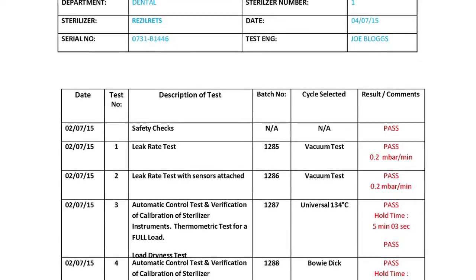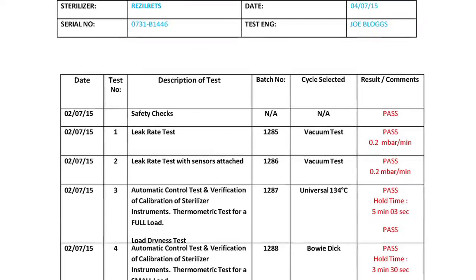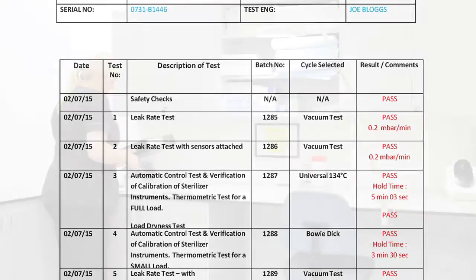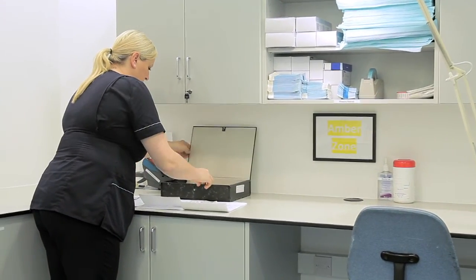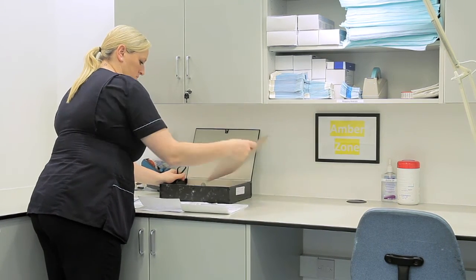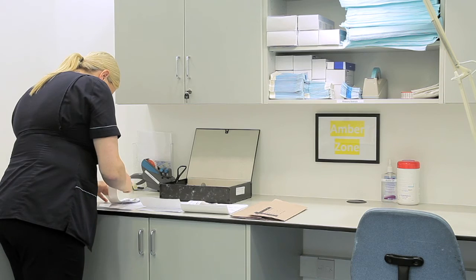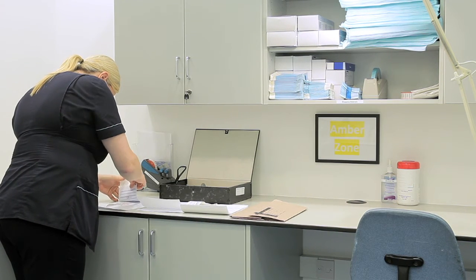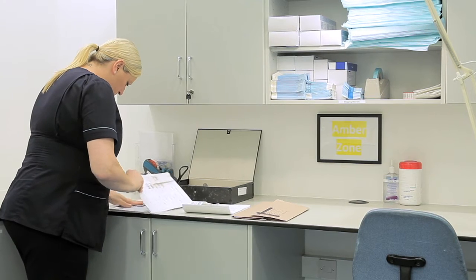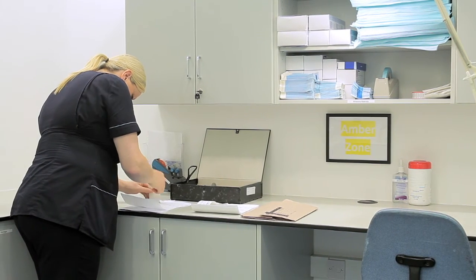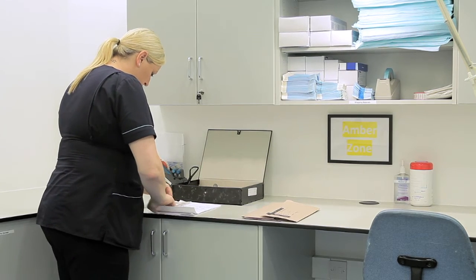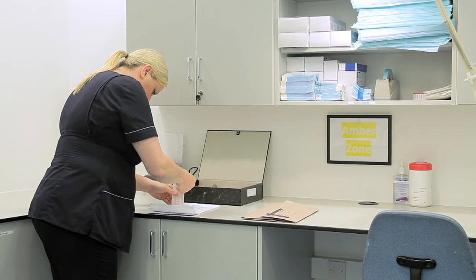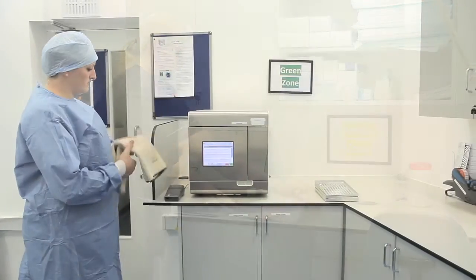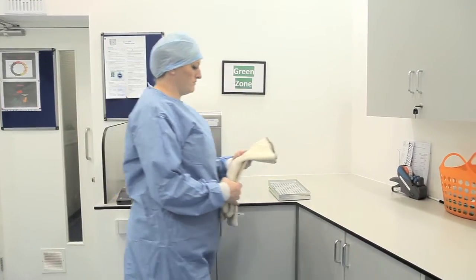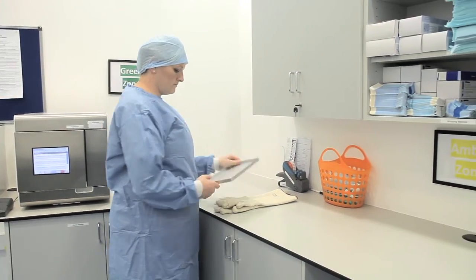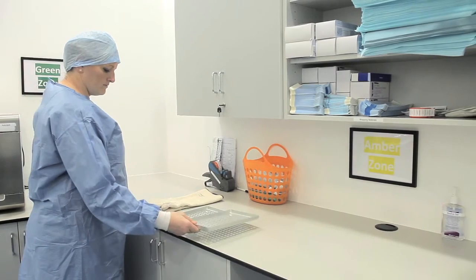If there are any failures of any of the cycles during the daily and weekly testing stage, ensure to report to the practice manager or decontamination lead. It is best practice to record and document all failures as part of the record-keeping files. If any of the daily or weekly tests fail, repeat each test again. If these repeat tests fail, do not use the autoclave. Contact the maintenance engineer to seek further advice. Once all daily and weekly tests have passed, you are now ready to process the RIMD through the autoclave. To do this, you need a tracking gun to label every packed instrument from the amber zone, which will then be placed in the autoclave trays.